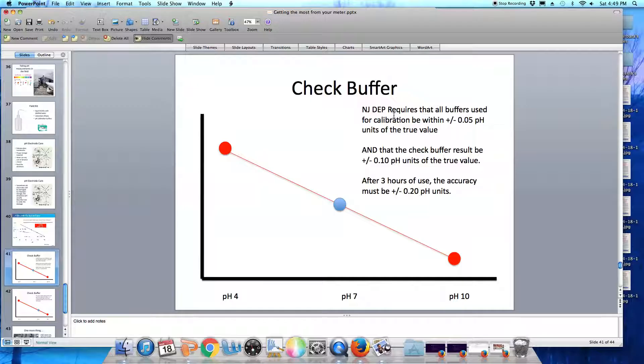The New Jersey DEP requires that all of the buffers we use for calibration be within 0.05 pH units of their true value. So if you buy a pH 4 buffer, the label says pH 4, but the actual value is 3.9, that would not meet this New Jersey DEP standard, and you shouldn't be using that buffer.